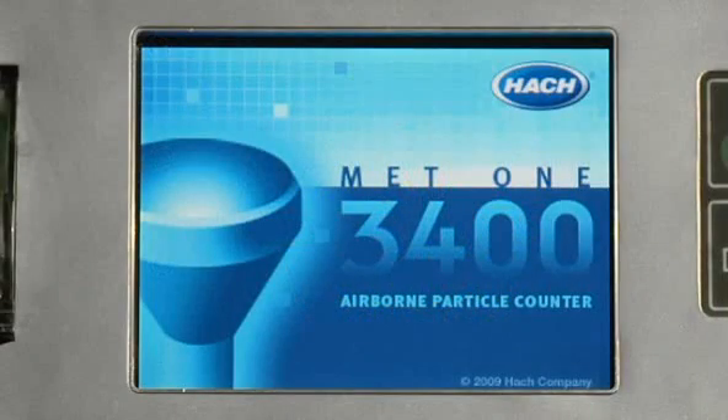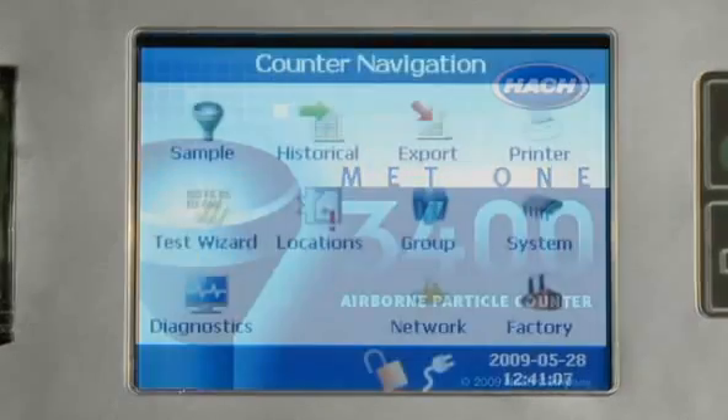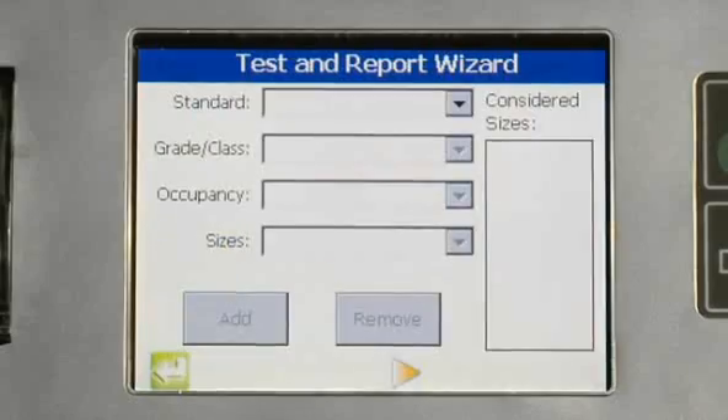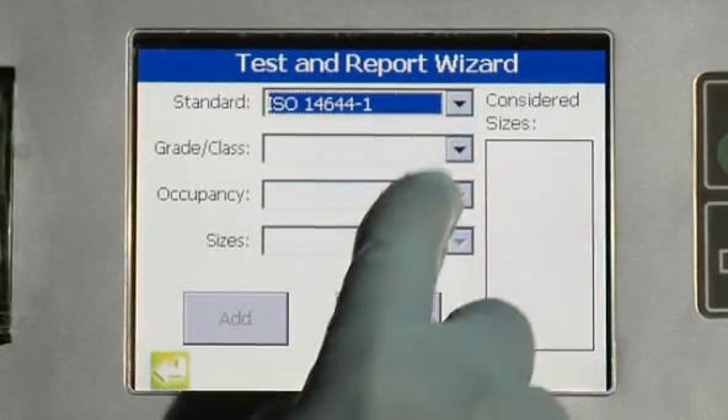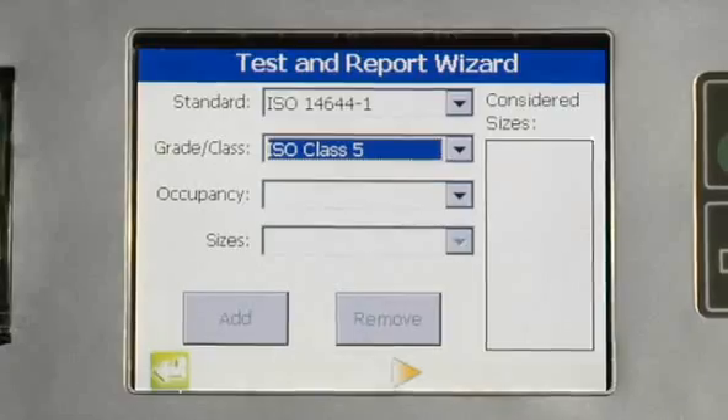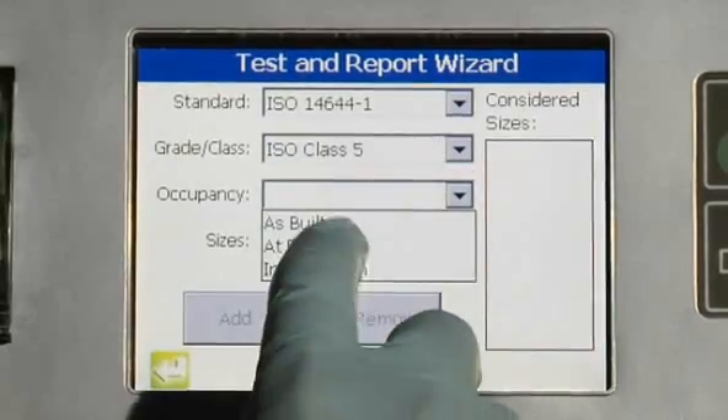The new MET ONE 3400 is easy to set up through the use of software wizards that guide the analyst to configure the instrument for Annex-1, ISO-14644, and many other common regulatory sampling requirements.